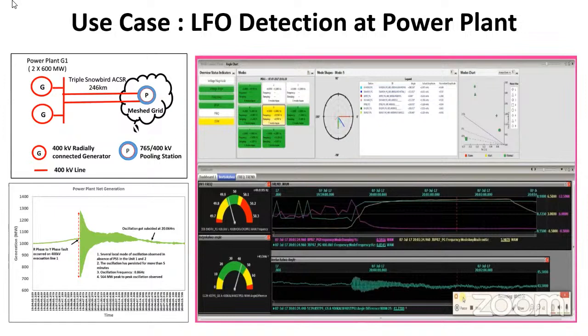Earlier it was not known whether the PSS was properly tuned or not. Based on this information, we contacted the plant and informed them that the tuning had to be checked against the network configuration. After that, retuning was done at that plant, and when a similar fault incident happened again, we didn't see any oscillation.